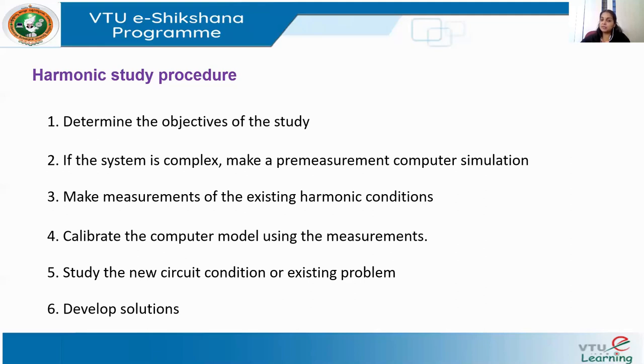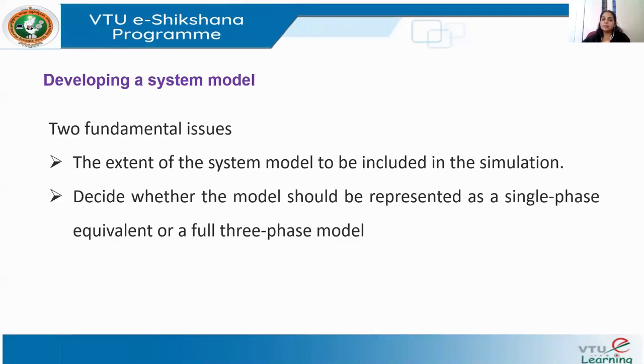The two most important steps in harmonic study are developing a system model and developing a model for the harmonic sources. When developing a system model for harmonic studies, there are two fundamental issues: first, the extent of the system model to be included in the simulation — how much of the system we need to include — and second, whether the model should be represented as a single-phase or three-phase equivalent.